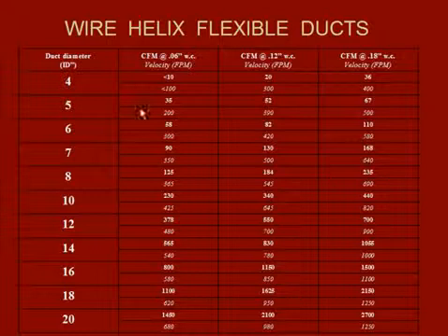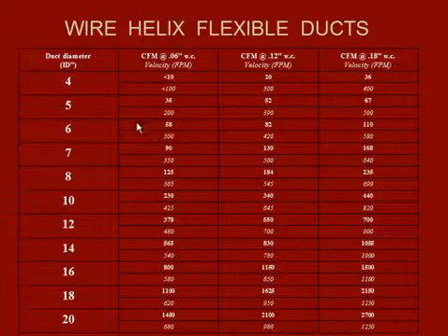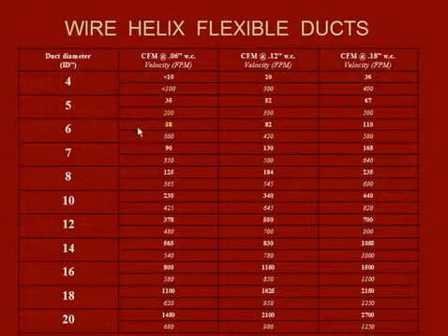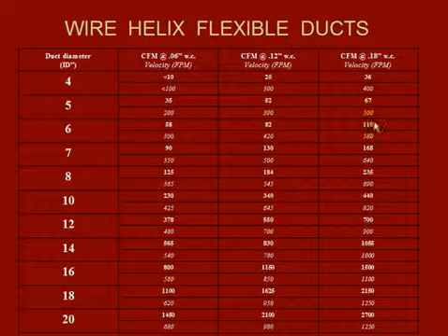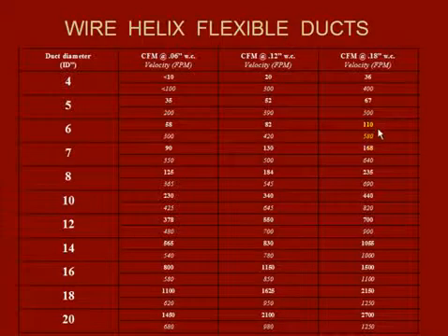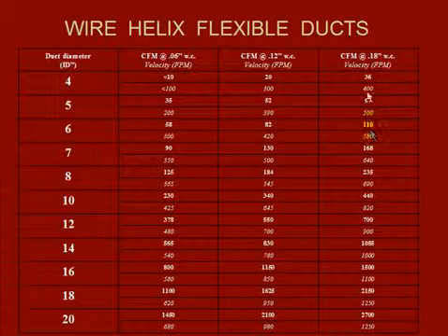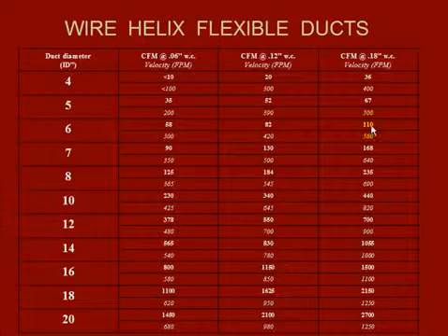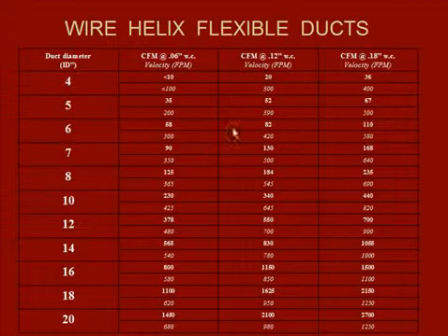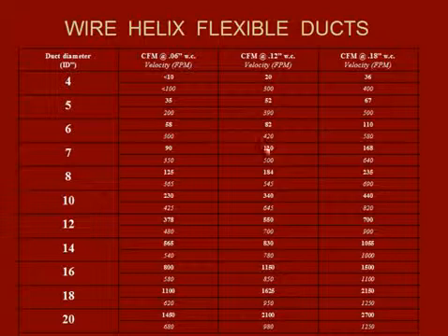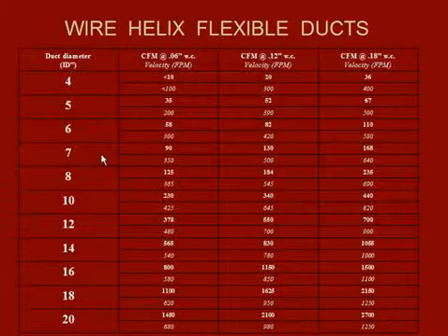And the reason is, let's say you wanted 100 CFM, 120 CFM. What size duct are you going to use? 6 inch round would probably do fine, but look at this, 120 CFM. You're all the way off the right side of the chart here that I'm going to explain to you in a minute, at 0.18. That's very high static pressure. That's noise. All right. If you want that same 120 CFM, you're going to be in this area. You're going to be in a 7 inch duct.